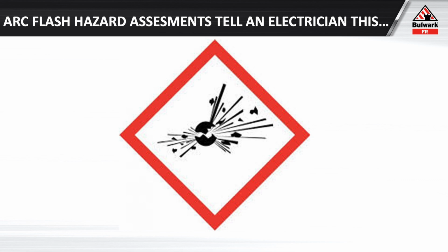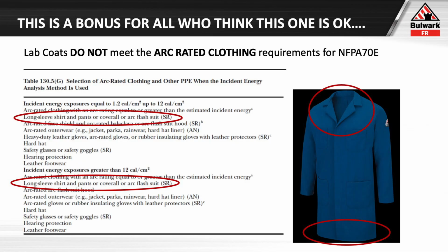Or am I in a substation where I've got potentially 32 calories of incident energy on the breaker I'm manipulating or working, or other electrical equipment? Because I'm going to dress differently. That's why we have 40-calorie suits available at our substations, but we're not putting our linemen in 40-calorie suits to go up in a bucket, because we know what the hazard assessment is.